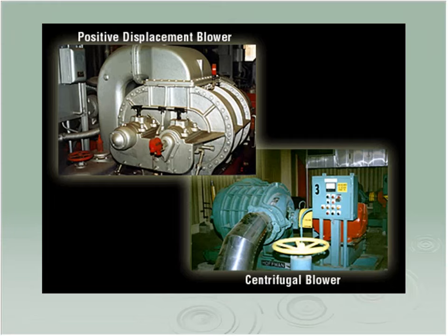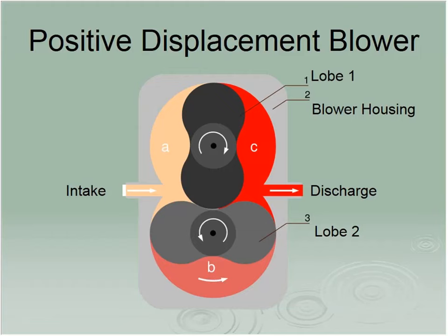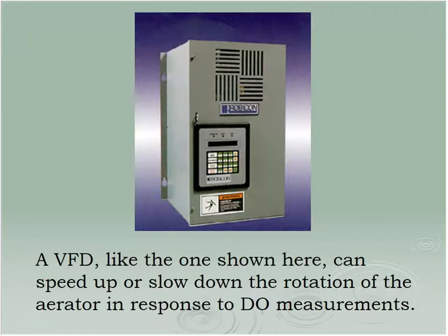A centrifugal blower is much like a centrifugal pump. You can shut that down for a while. The fans will just spin. It won't really cause much of an issue. There's a big PD blower, a big Roots type of blower. See that silver unit on the far end, the pressure relief, just in case by some means the valves get shut. It won't blow everything apart. Rupture your eardrums. Well, a very tight displacement. You can't get a piece of paper between those two lobes at that location. Air comes in, gets pumped up, and pushed out.